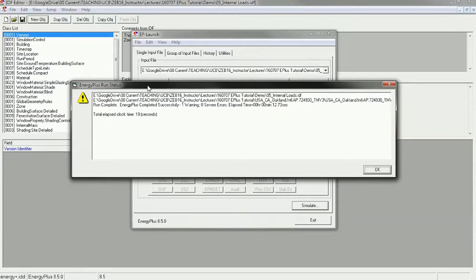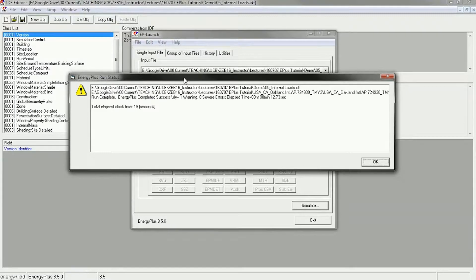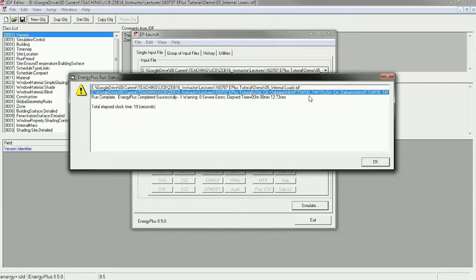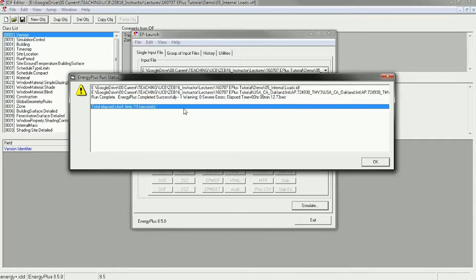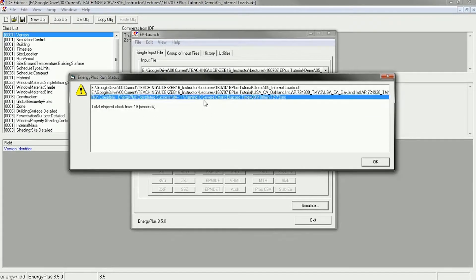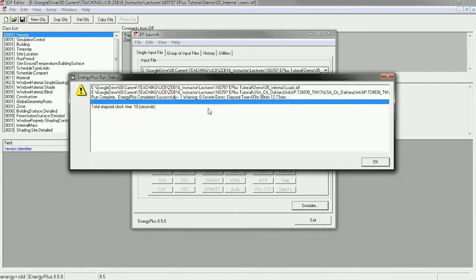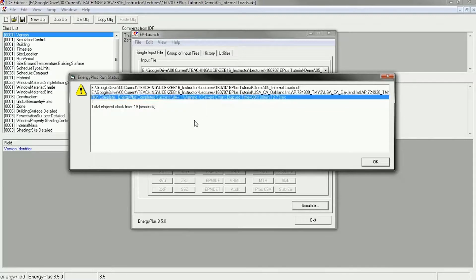It's extremely important when you get this dialog box to read it carefully and make sure that it ran as you expected. It tells you the two input files — the internal loads IDF and the weather file — and then it says run complete: EnergyPlus completed successfully, one warning, zero severe errors, elapsed time 12 seconds. The first thing you should do is jump for joy because you have zero severe errors — that's wonderful and cause for celebration.